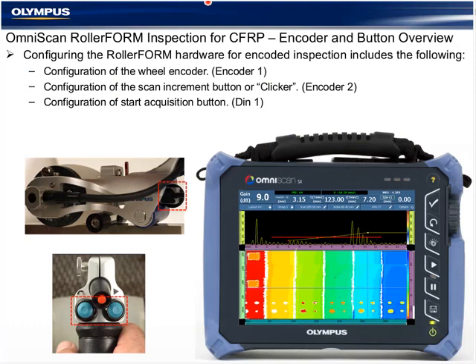The next part of the presentation, and this is a separate presentation in the follow-up files that you'll receive from this webinar, is a configuration of the hardware on the RollerFORM wheel probe with the OmniScan. So that's going to include the configuration of wheel encoder 1, which is associated to the scan axis. It's going to configure the increment button that we see here on the RollerFORM that works as a clicker on encoder 2. And it will include the configuration of the DIN, or digital input button, for start acquisition and clear inspection, for repetitive inspections without having to touch the instrument.